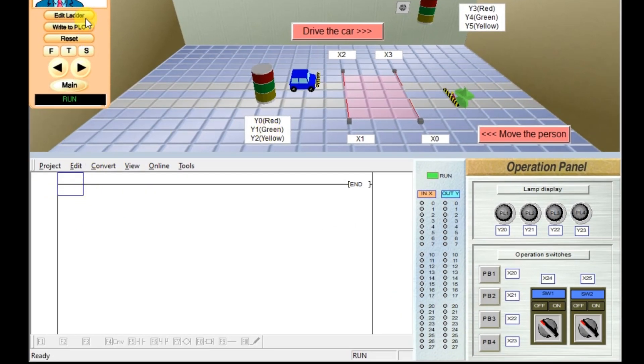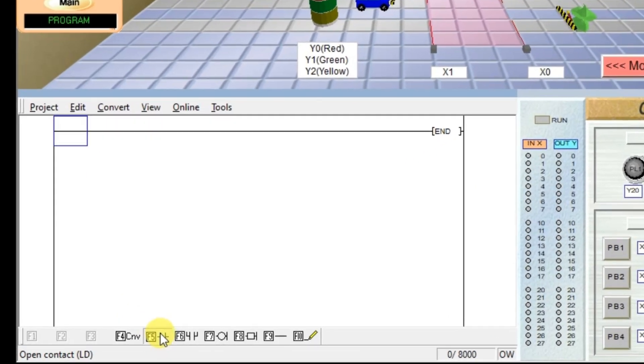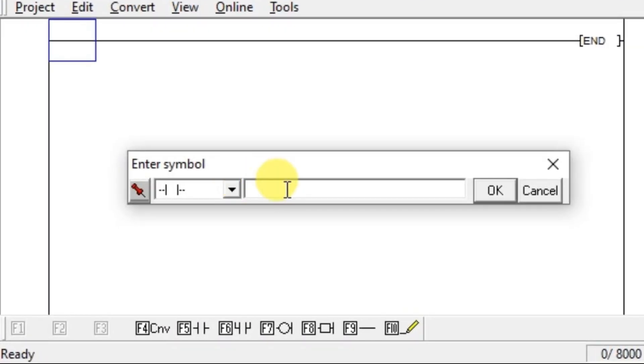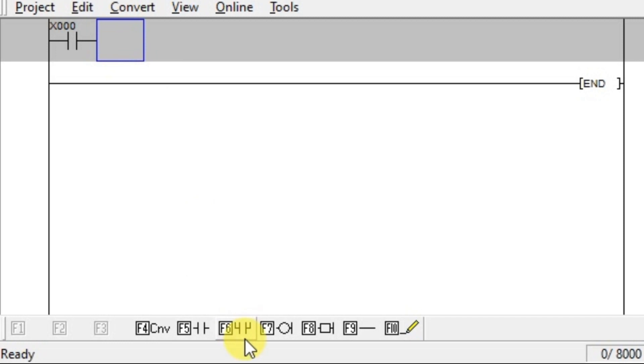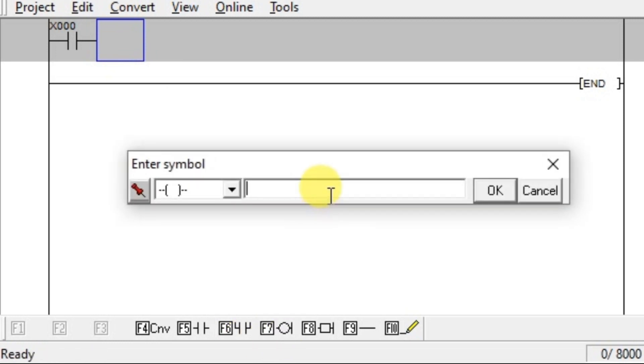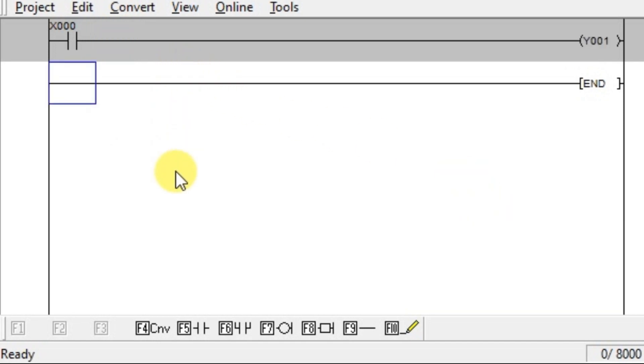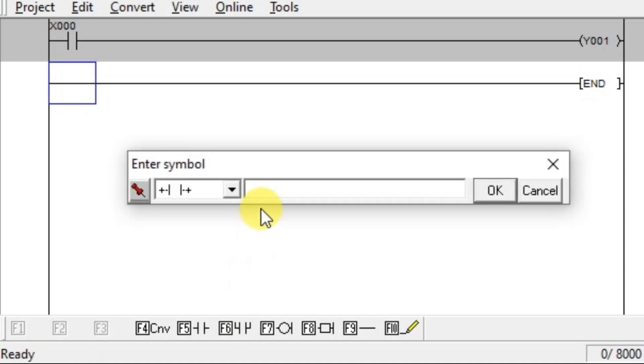Click Edit Ladder so the program will change. Take one NO contact and enter the entry sensor address, which is X0. Then we have to turn on the green lamp, so take one output coil instruction and enter Y1. As the input sensor X0 will give you only a single pulse — whenever the person enters, the sensor turns on; whenever the person left from the entry sensor, the sensor turns off again. It is not a continuous signal, so we have to latch the output Y1. Take one branch instruction with NO contact and enter output address Y1.